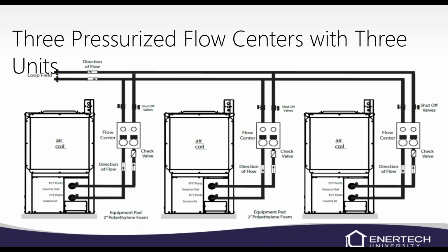If you had, let's say, 20 units in a big building, I probably wouldn't do flow centers. I would probably do one standard, maybe variable speed pump in the whole building, and then have zone valves or whatever for each unit to call at that time to supply the flow. But if you get into a bigger job like that, definitely get with your TM or tech support. We can give you a hand on the best way of flowing water for those systems.